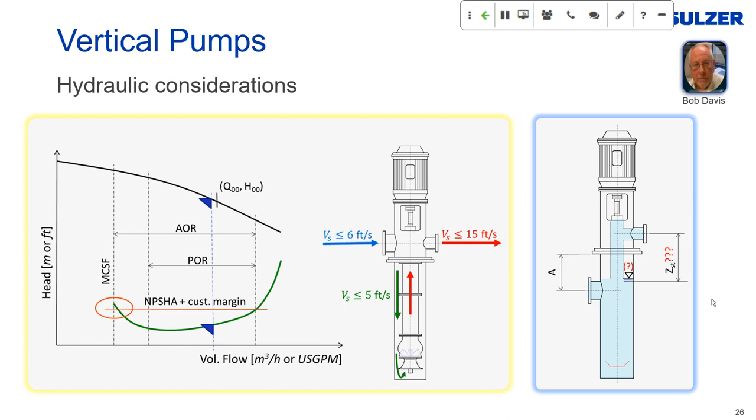Many customers want to replace an existing pump but continue using the same suction can. We can either re-bowl with new custom hydraulics or replace the entire pump with new technology, using just a data sheet and GA drawing. However, we get into trouble when the retrofit involves higher flows, because higher flows mean higher velocities in the can that can exceed Hydraulic Institute standards — and this is where computational fluid dynamics becomes very useful. One would think that with Sulzer's hydraulic range coverage there would never be a need for new hydraulics, but new hydraulic performances are routinely required.